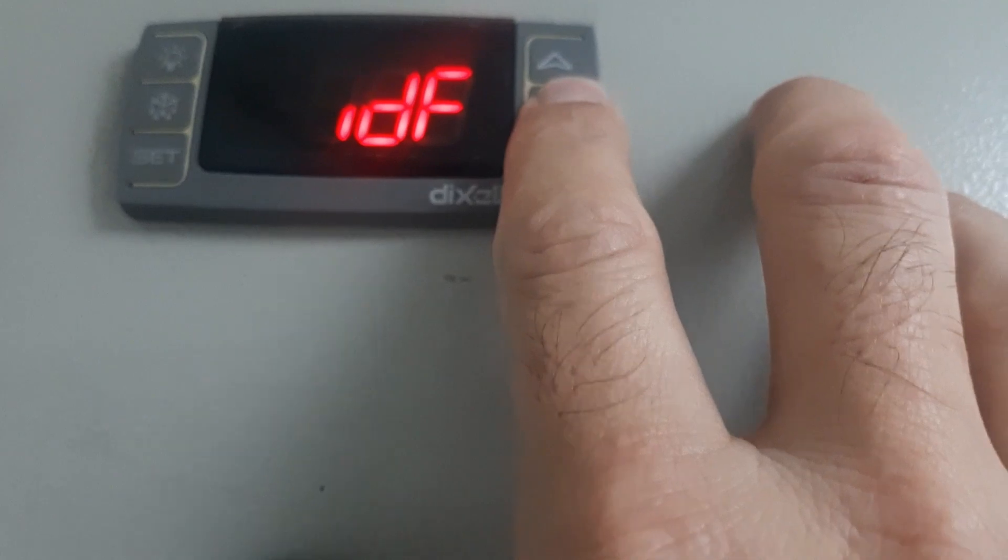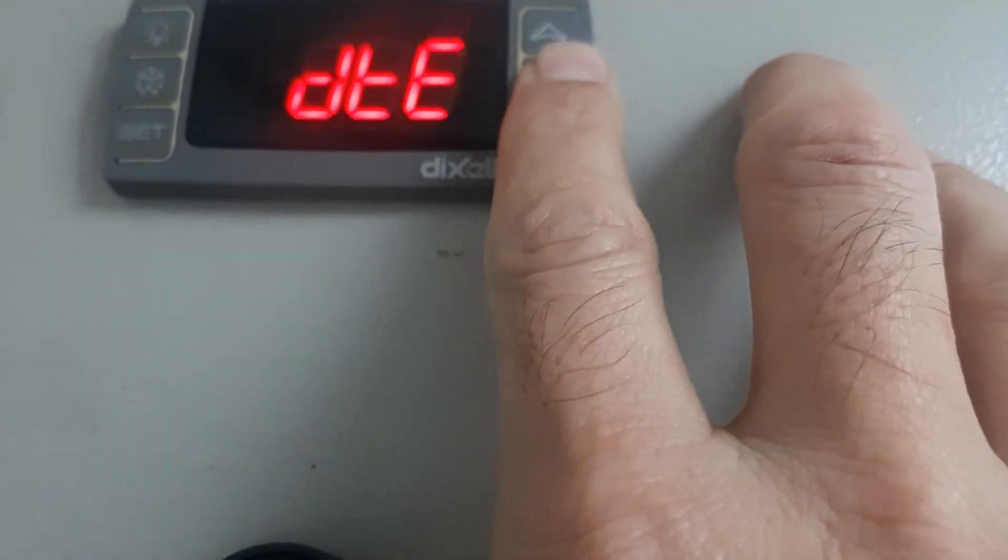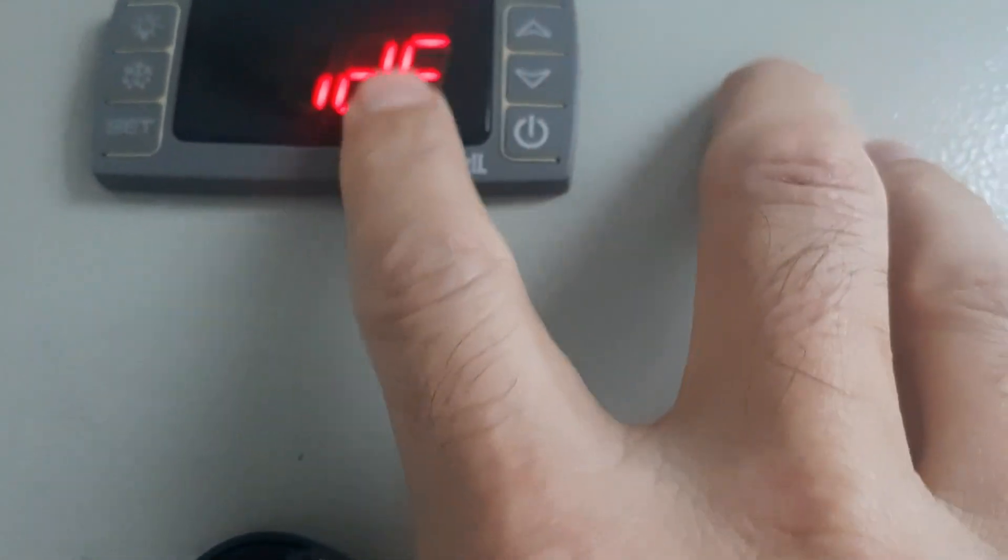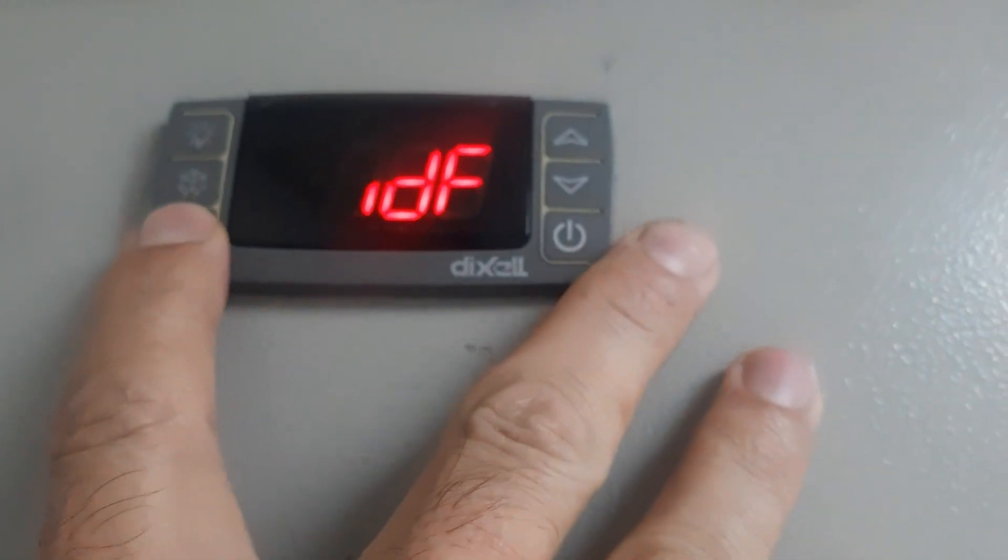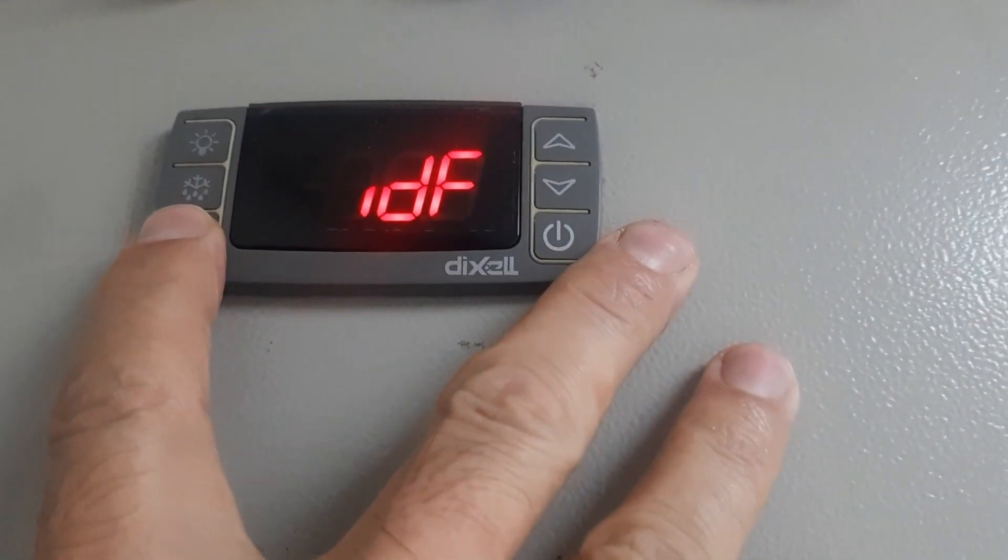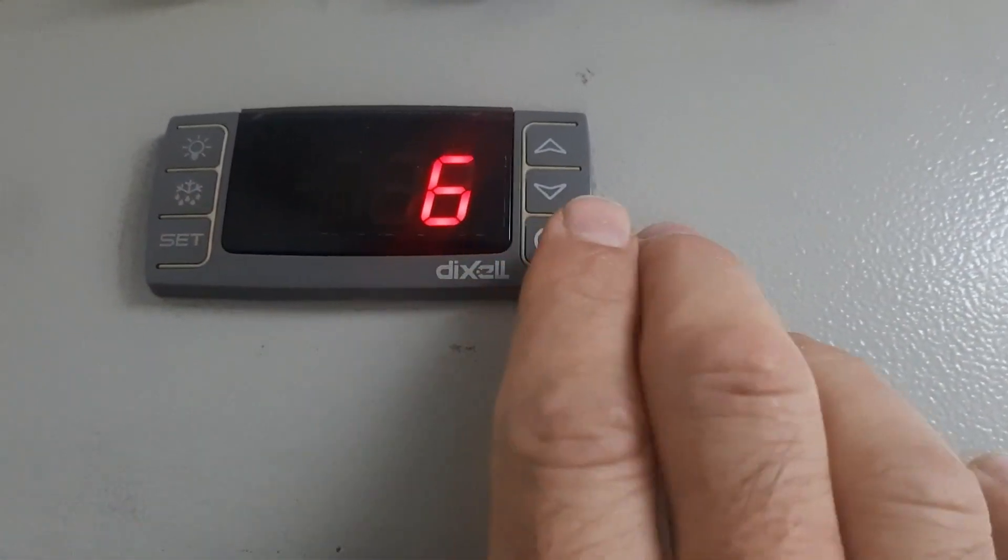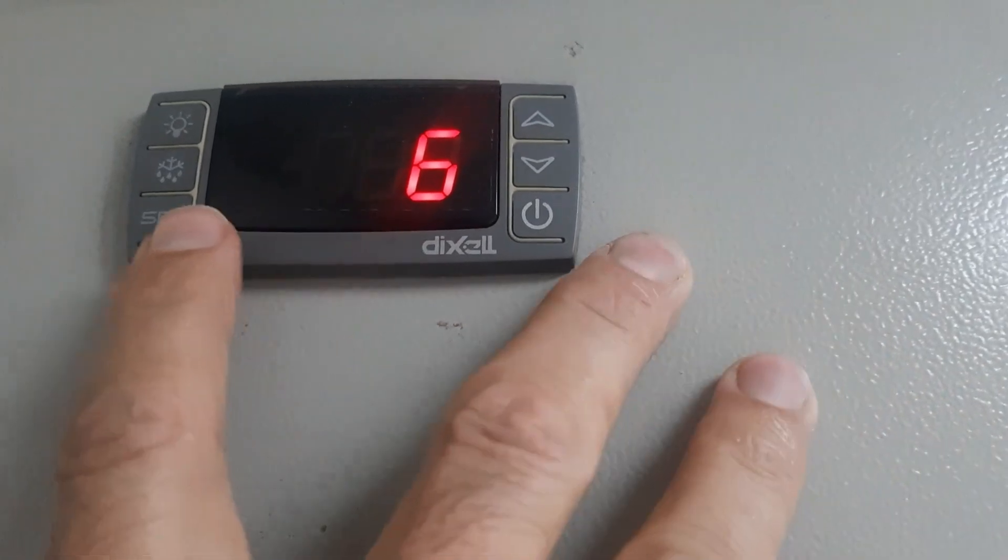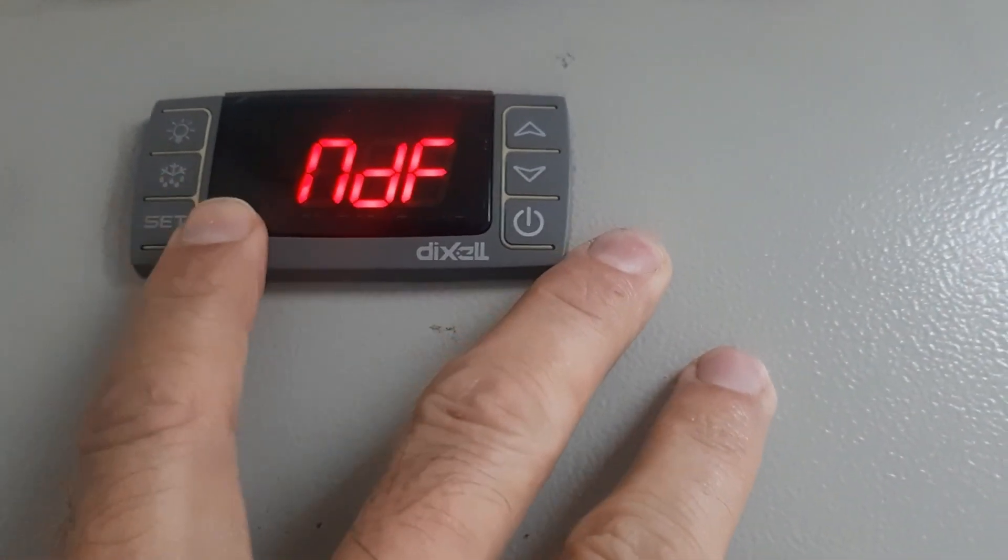And here this is defrost setting, I will show you defrost hour, IDF. IDF means defrost hours, 6. After 6 hours your cold room will go for defrost, 30 minutes.